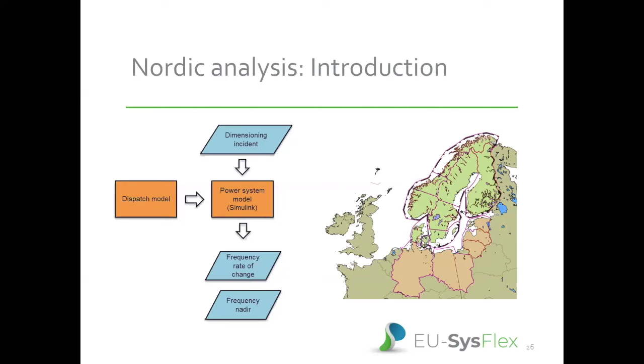Okay, and then we go to results. Here you can see the results of frequency nadir for these 3 different scenarios. For the Nordic system, the limit for the minimum frequency nadir has been set as 49.0 Hertz. And as you can see, it was not reached in any of these cases, but the margin is quite small, especially in high solar and renewable ambition scenarios.